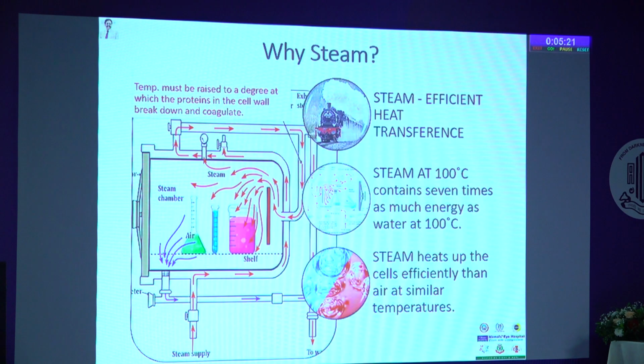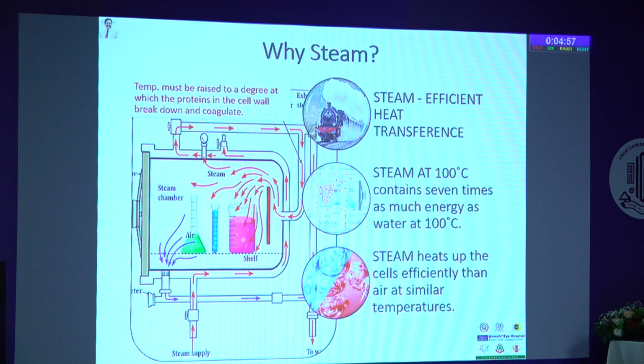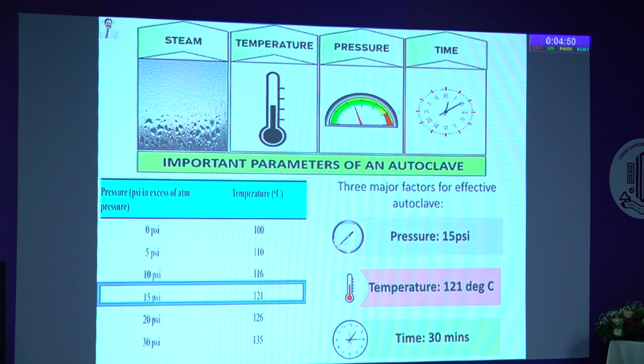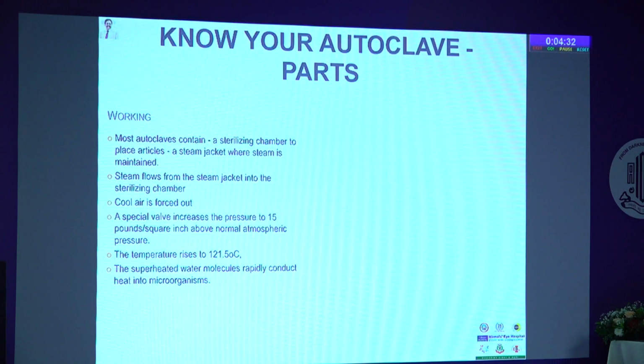So why steam, why not chemical? This is an often repeated question and discussion in many forums. Steam is an efficient heat transference mechanism. That's why we started with the steam engine, and the same principle goes on even now. Steam at 100 degrees contains 7 times as much energy. So this is also an energy saving device, and once it heats up cells efficiently, living organisms like bacteria or spores are killed. Those are 3 important parameters. Whatever autoclave you buy, all these autoclaves work on these 3 parameters, and this is the most repeated setting for an autoclave: pressure at 15 psi, temperature 121 degrees, and time of 30 minutes.